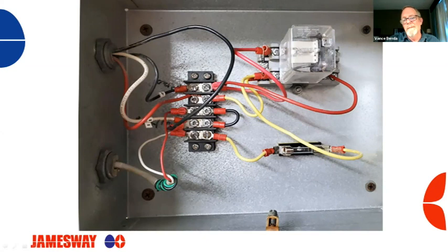So once again, I told you in a series wired alarm system, your DC voltage has two choices. When it gets to here, you see your parallel wiring. The positive terminal is connected to both terminal B of your relay, and over here, it's connected to a normally closed contact on the top tier of your relay, which means anytime this relay loses power, voltage is going to go through this normally closed contact right on that yellow wire and go out and blow your horn. If voltage goes out on your loop and makes it back, this relay is going to latch and the horn is going to be silenced. So once again, your battery's always doing something. Your power supply is always doing something in the fail-safe alarm system.